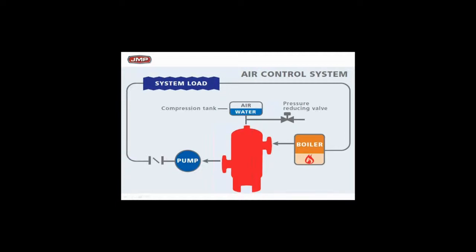The compression expansion tank has to be above the air separator so air can move back and forth by gravity. This is a system you'd see in about five to ten percent of installations — you're going to see these primarily on older projects. They work great.